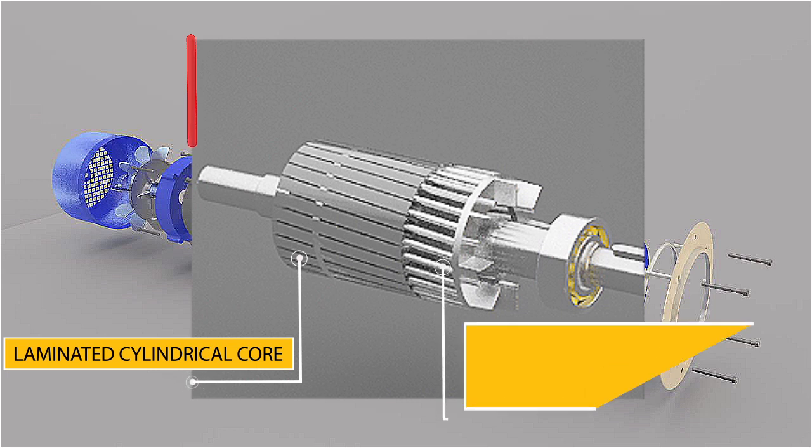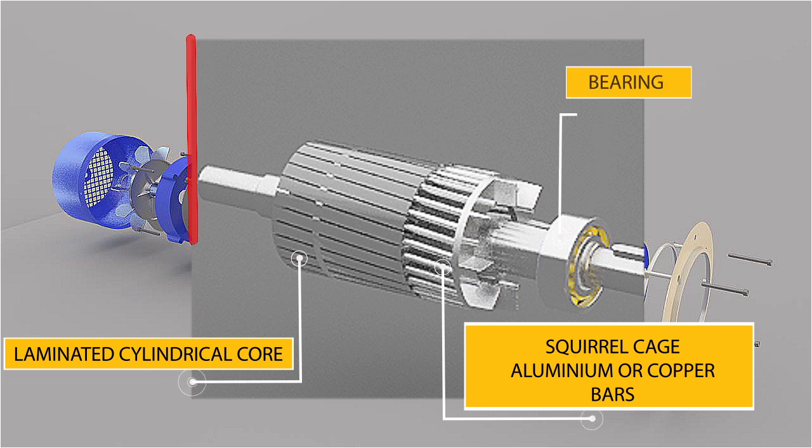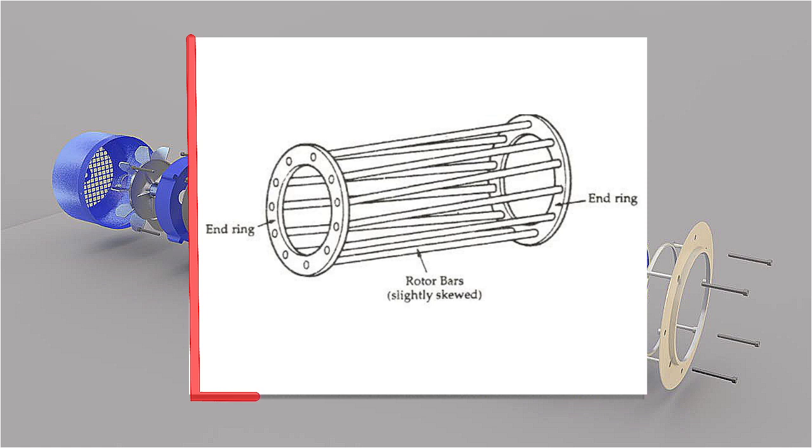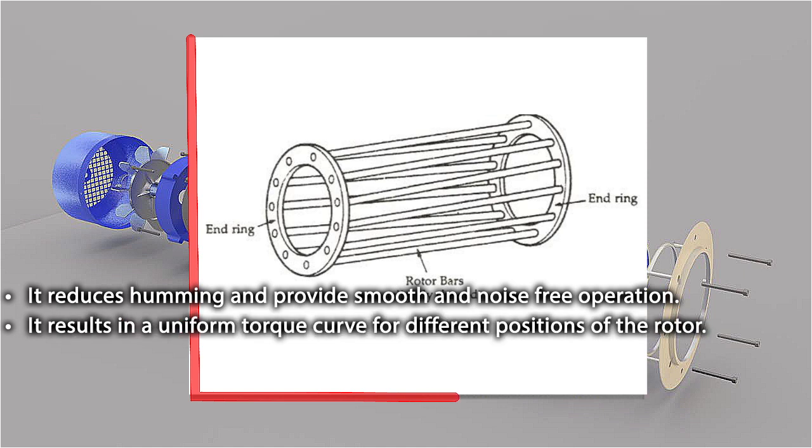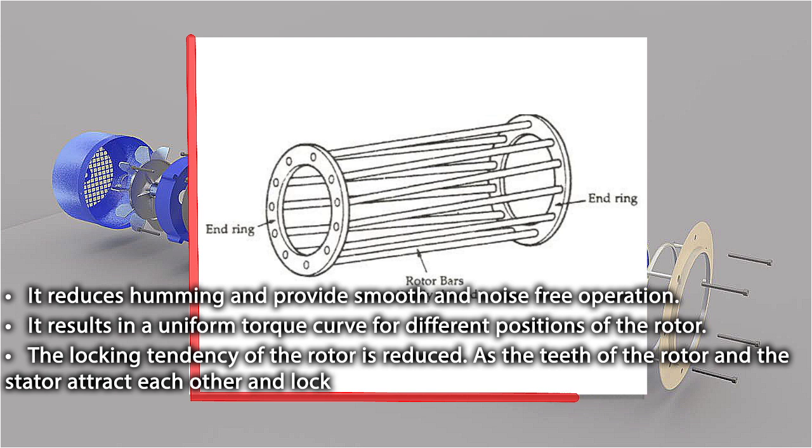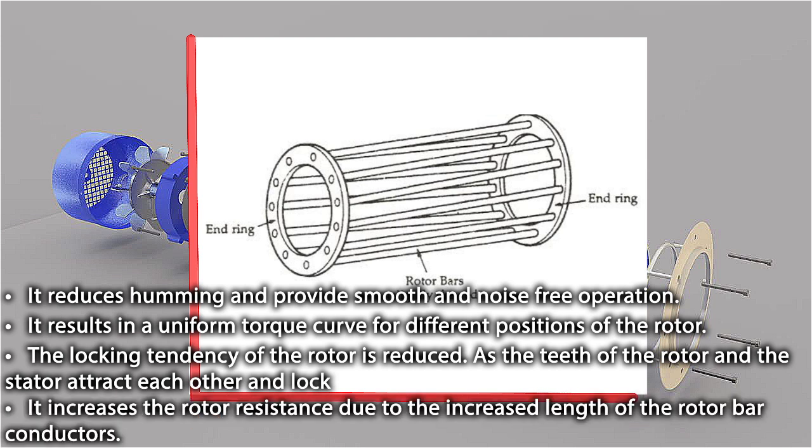A squirrel cage rotor consists of a laminated cylindrical core. The circular slots at the outer periphery are semi-closed. Each slot contains uninsulated bar conductors of aluminum or copper. At the end of the rotor, the conductors are short circuited by a heavy ring of copper or aluminum. The rotor slots are usually not parallel to the shaft but are skewed. The skewing of the rotor conductors has the following advantages: It reduces humming and provides smooth and noise free operation. It results in a uniform torque curve for different positions of the rotor. The locking tendency of the rotor is reduced, as the teeth of the rotor and the stator attract each other and lock. It increases the rotor resistance due to the increased length of the rotor bar conductors.